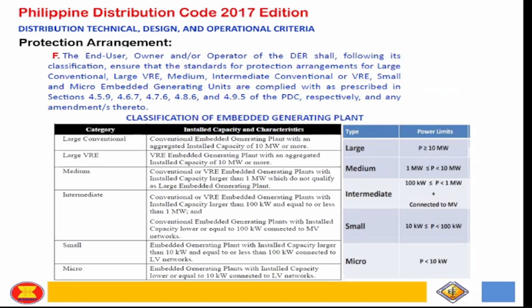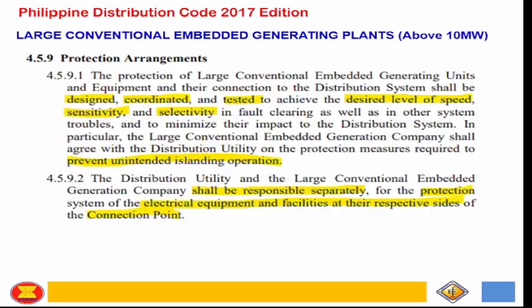The small and micro are at the LV side, at the low voltage network. Then there's a provision on protection arrangement for the large conventional generating plant, 10 megawatt and above. But there's nothing specific about what the protection scheme is. What is mentioned is that it shall be designed, coordinated, and tested to achieve the desired level of speed, sensitivity, selectivity, and also prevent unintended islanding. It's medium general, but later there are protection schemes for the types of generator.